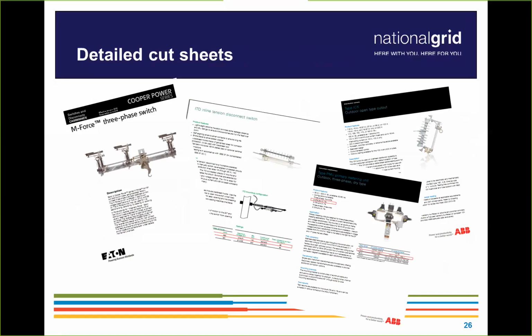Now, we would require that three-phase switch cut sheet to be submitted to us because there are items that would be described on the cut sheet that you could describe on the drawings, but we want to confirm that they meet our standards, such as mechanical stressing of equipment for our three-phase switch installations on the cross arms on the poles for your point of attachment. Items such as the load breaking capability or fault current or interrupting duties on equipment. The voltage rating of insulators, or the BIL rating, to make sure that the BIL ratings are meeting our minimum standards.